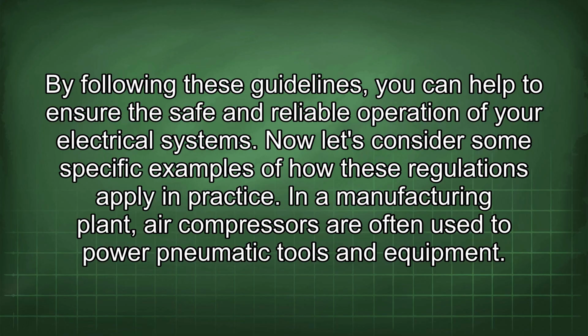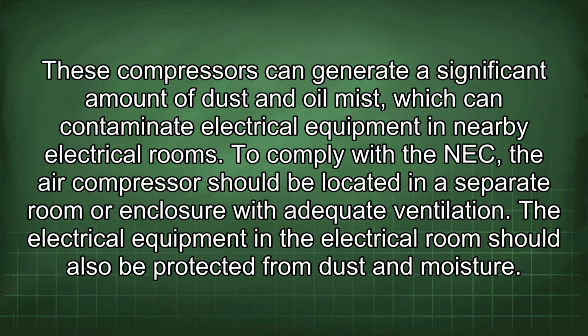Now let's consider some specific examples of how these regulations apply in practice. In a manufacturing plant, air compressors are often used to power pneumatic tools and equipment. These compressors can generate a significant amount of dust and oil mist, which can contaminate electrical equipment in nearby electrical rooms. To comply with the NEC, the air compressor should be located in a separate room or enclosure with adequate ventilation. The electrical equipment in the electrical room should also be protected from dust and moisture.